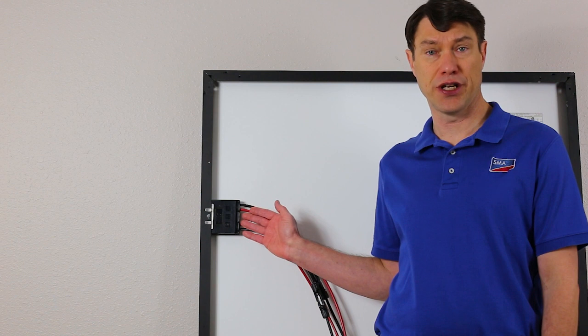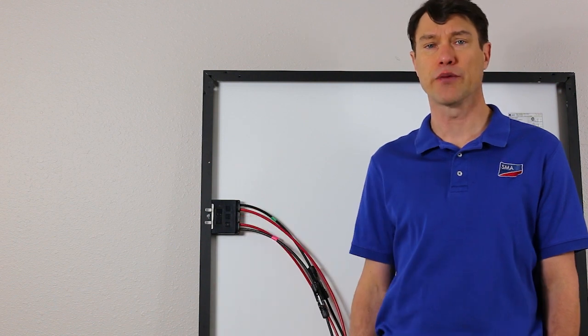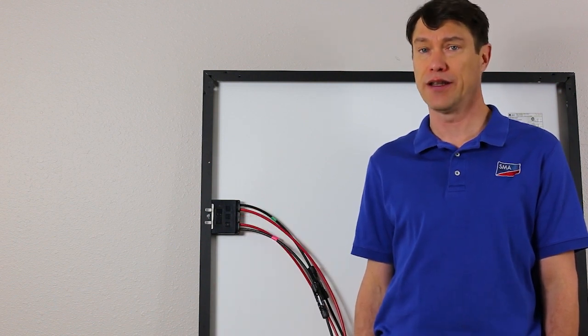It's important to remember that the SunSpec shutdown receiver will stay in shutdown mode until it receives the keep-alive signal from the transmitter built into the inverter. That is, independent of the VOC of the module, the output leads will measure only one volt DC until the receiver receives the keep-alive signal.